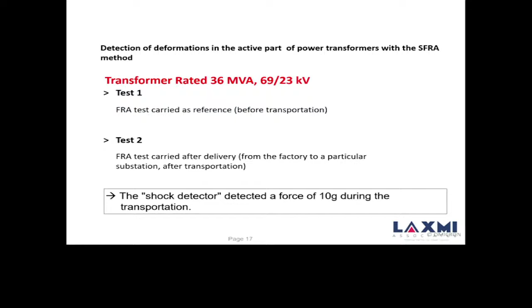Third case, a 36 MVA industrial transformer. Before and after transportation we have fingerprints, and this fingerprint is slightly confusing, with deviations in both the HV plot and the LV plot. We concluded something happened in the neutral connections, not that the whole HV-LV winding was bad. That suspicion was true, because it was on the LV side, nothing could be done at site, so it went to the factory. We found the support for the leads was not sufficient, and during transportation the lead came down because supports weren't proper, with 90-degree bends. Such bends without sufficient support are, by design, not good for short circuit withstand capability.